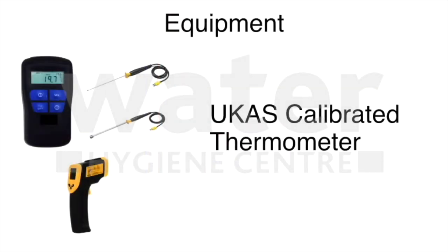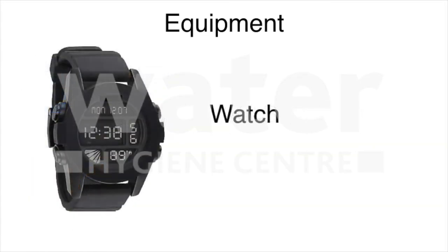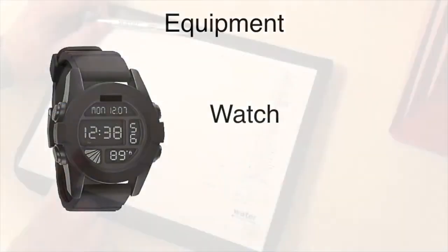You will need a UKAS calibrated thermometer. These come in many shapes and sizes, with surface or immersion probes. You can also use infrared thermometers to take temperature readings on pipework surfaces. These should be used in line with the manufacturer's guidelines. Always check that your thermometer calibration has been completed and that the calibration is in date before using it. You will also need a watch to monitor the time spent taking the temperature.